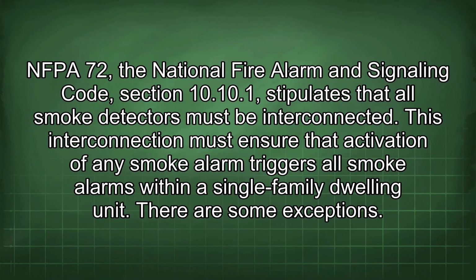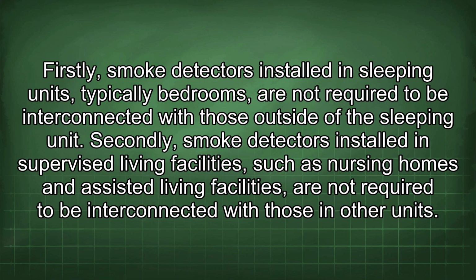NFPA 72, the National Fire Alarm and Signaling Code, Section 10.10.1, stipulates that all smoke detectors must be interconnected. This interconnection must ensure that activation of any smoke alarm triggers all smoke alarms within a single-family dwelling unit. There are some exceptions. Firstly, smoke detectors installed in sleeping units, typically bedrooms, are not required to be interconnected with those outside of the sleeping unit.